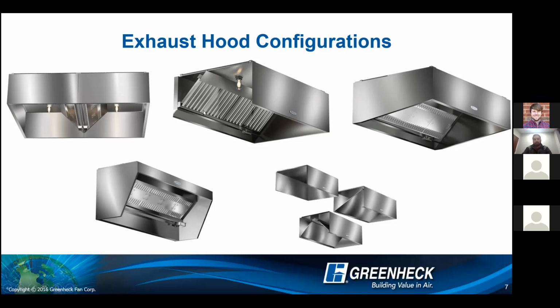The final configuration would be a type 2 or a heat/condensate hood. So again, this would be a type 2 application. You can have condensate baffles in these to knock down condensate over dishwashing applications.